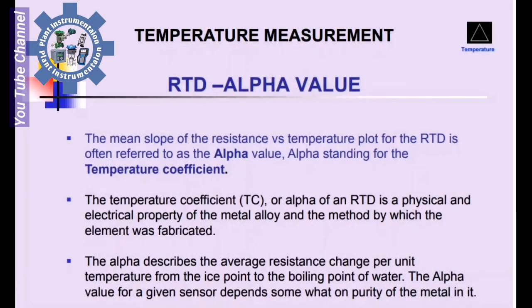RTD Alpha Value: The mean slope of the resistance versus temperature plot of the RTD is often referred to as the alpha value. Alpha stands for the temperature coefficient. The temperature coefficient, Tc or alpha, of an RTD is a physical and electrical property of the material alloy and the method by which the element was fabricated.